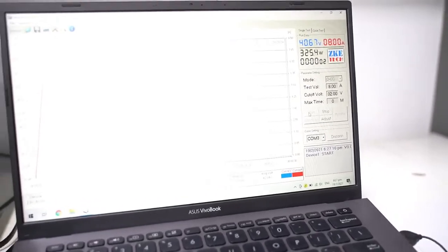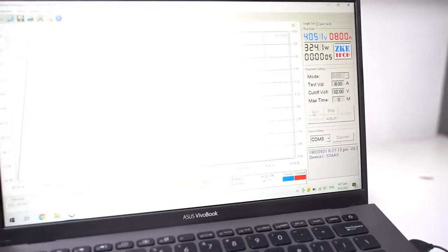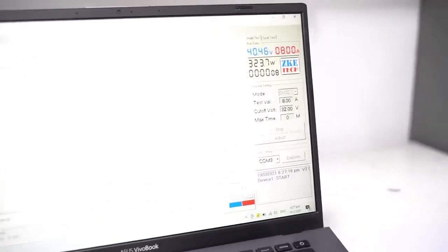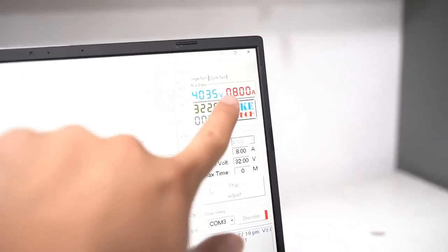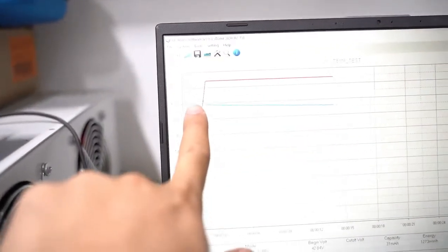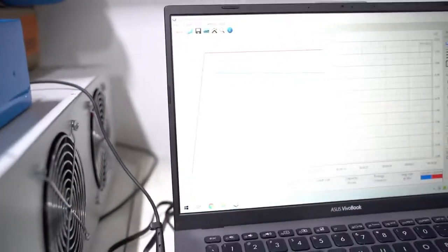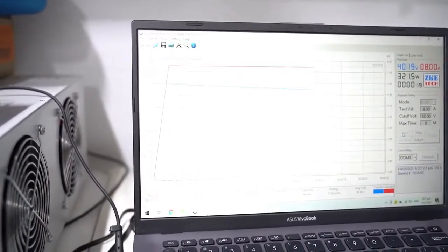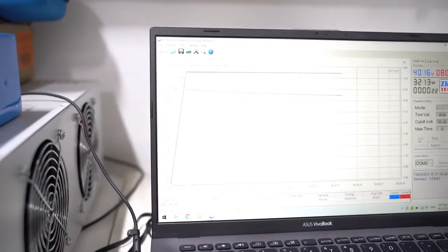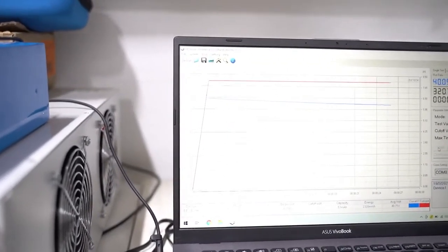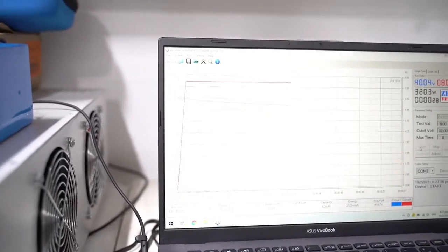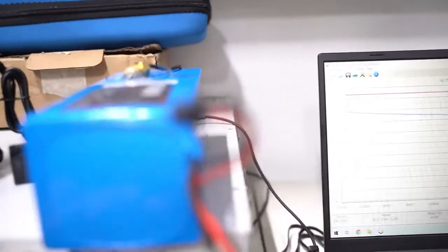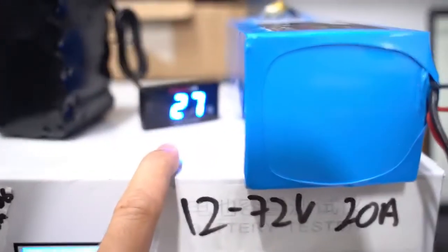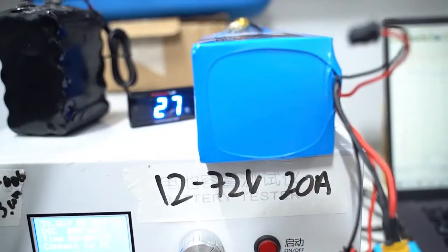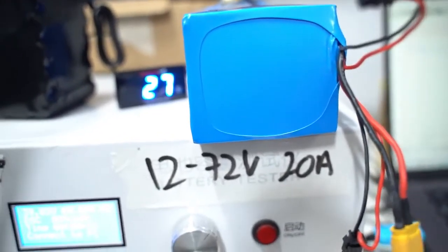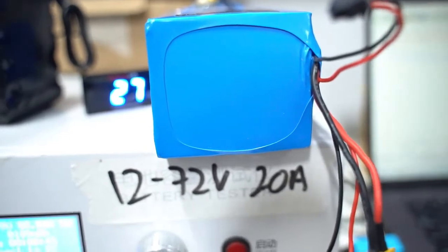Okay, so the fan is running because the load resistance is kicking in, and you can see it's running at 8 amps, and there you see the dip. We're not running at 13 amps like before because the dip was just too much. It didn't really prove to be a conclusive test. So we are just running at 8 amps right now. You can feel the battery is getting hotter as the discharge across that load is activated. We'll wait for a couple of minutes and then check back.